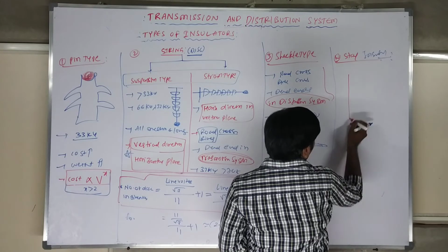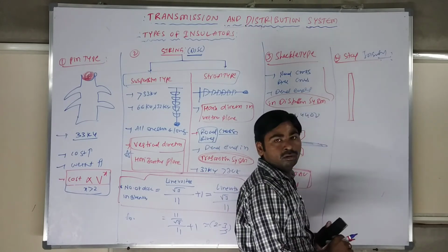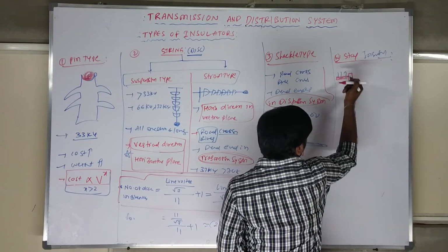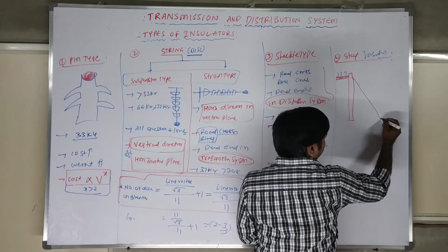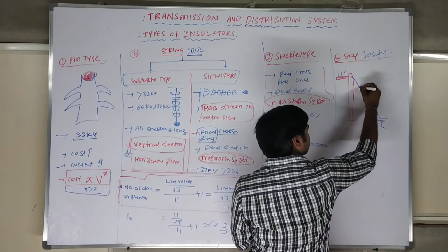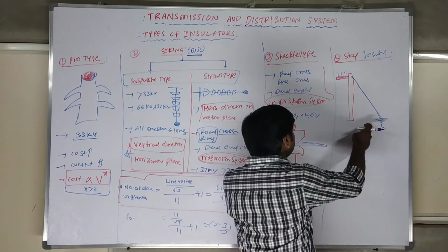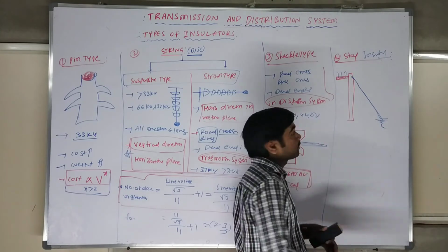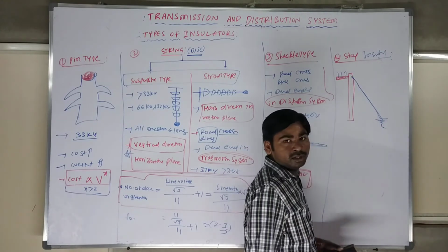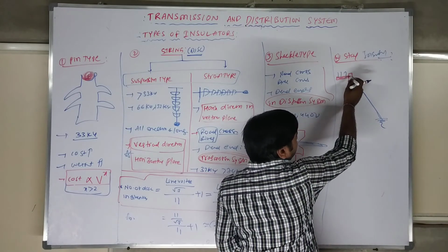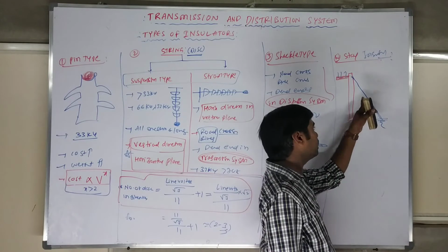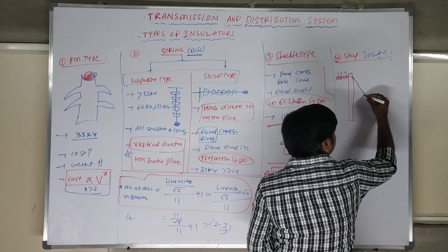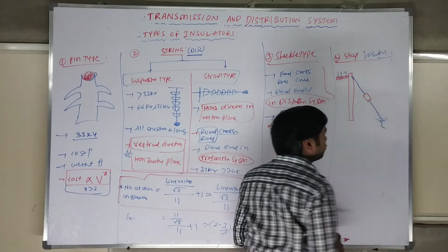Basically, in village applications, we have a pole with a cross arm, carrying the transmission line. For this, we require a stay wire on the ground side. It is a supporting wire connected to your pole. Sometimes the earthing system or insulator may fail or get damaged, and there may be chances of shock. Then current can flow into the stay wire also. To protect against this, you connect one insulator in the stay wire.